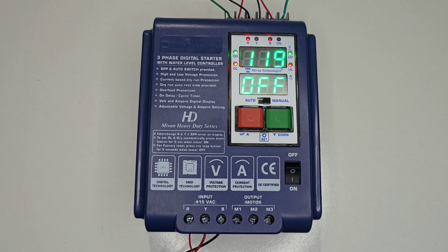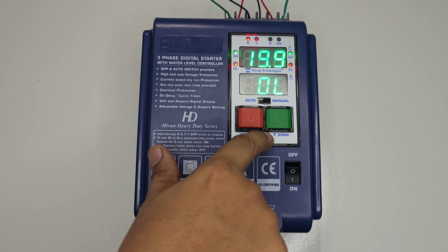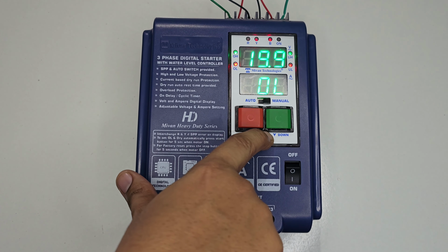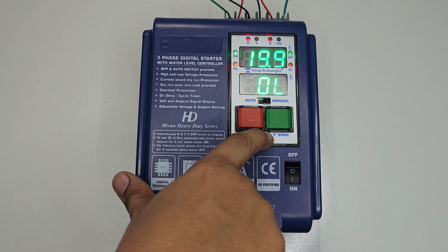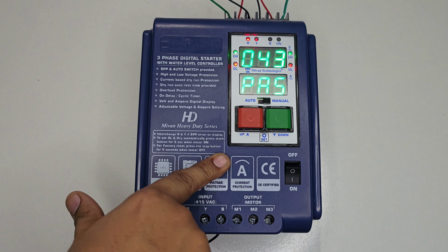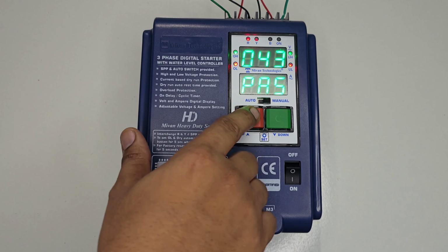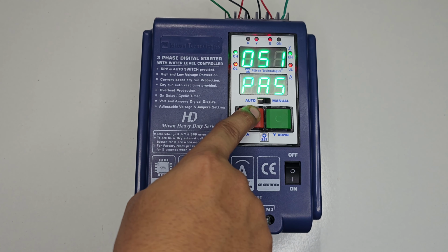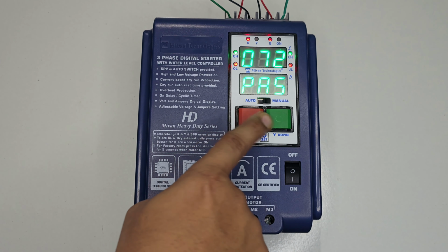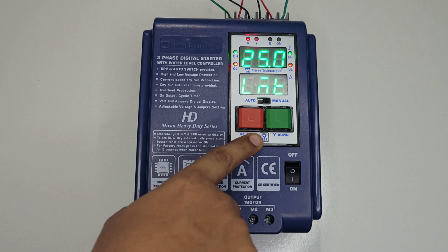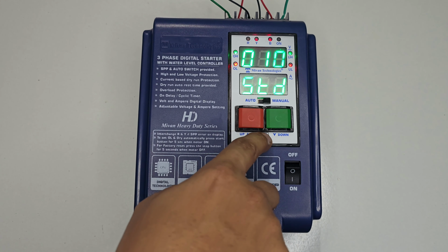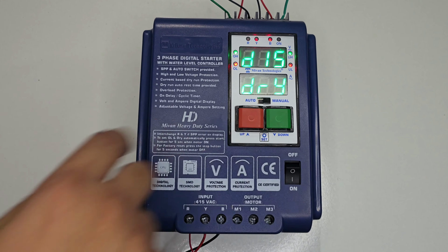Now I'll show you how to set the dry running current. To set the dry running current, first you need to enable the dry running option from the password. Press the set button for 5 seconds. You will be asked for the password. Go to the password 70. Press the set button. Again press the set button.